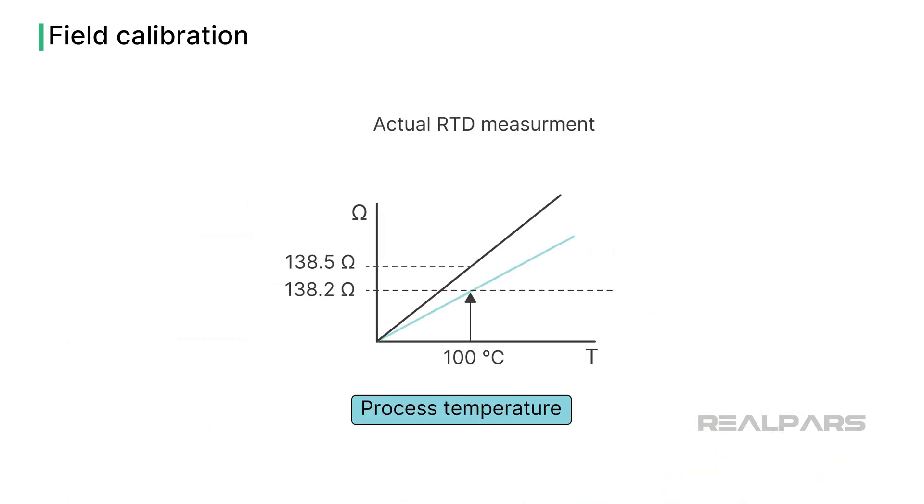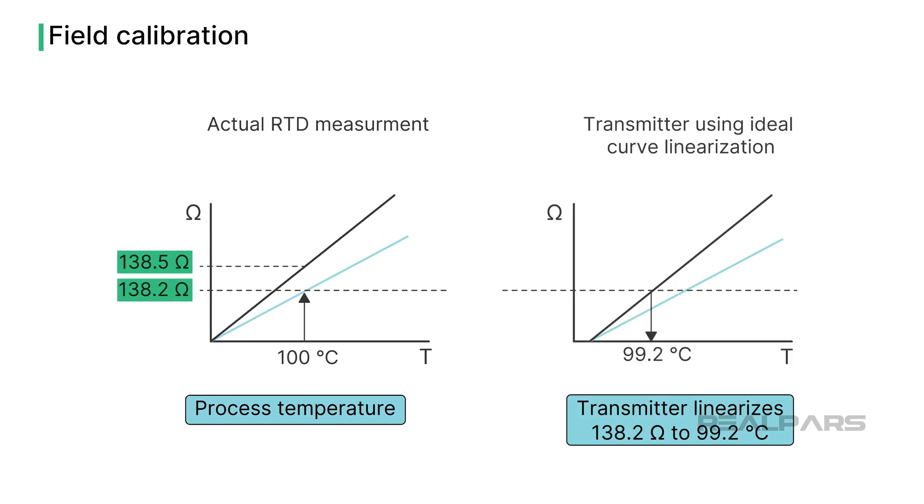RTDs cannot be adjusted to compensate for inaccuracies. So offset or scaling corrections are required if the transmitter is capable. It's worth noting that applying a correction factor in a PLC or DCS is often possible.